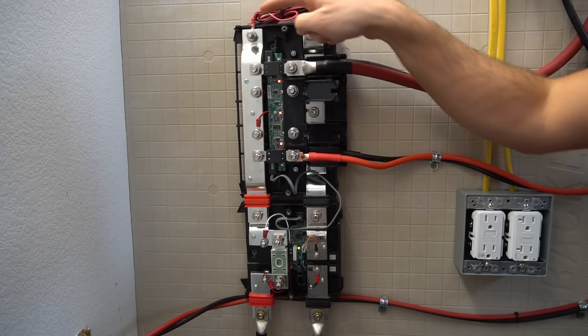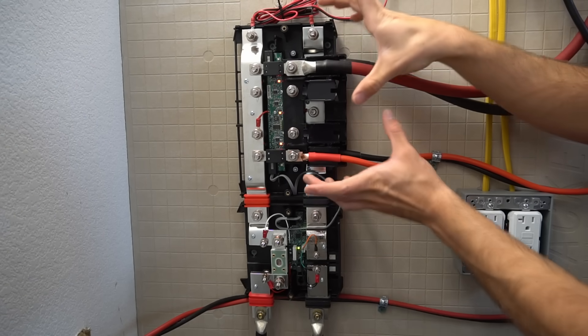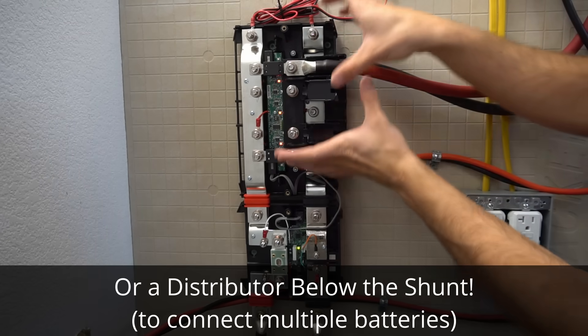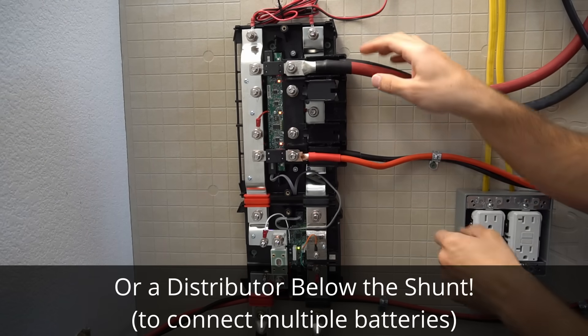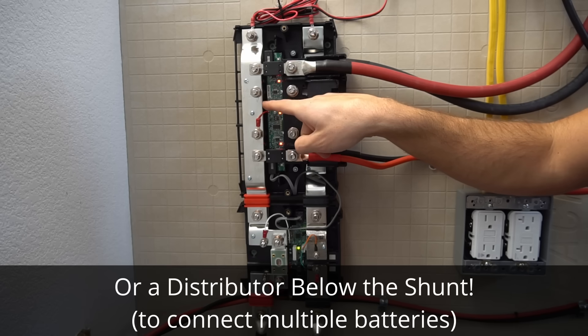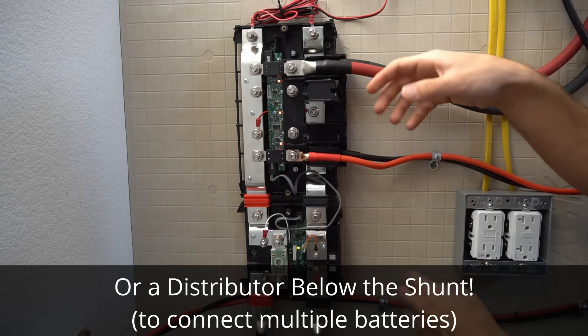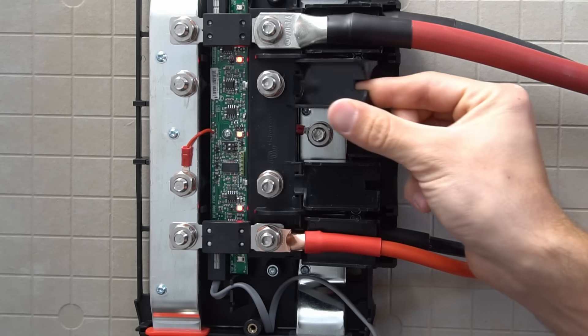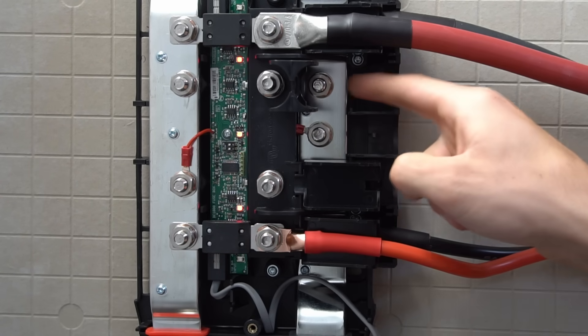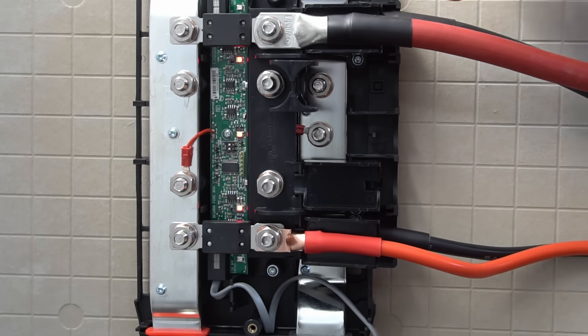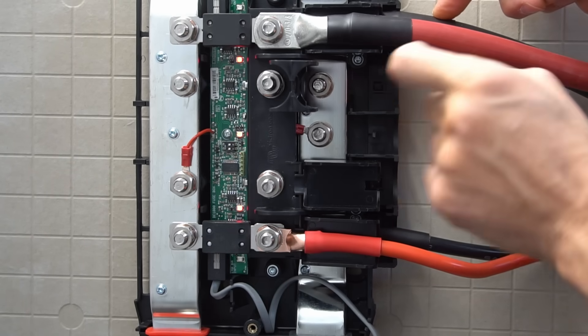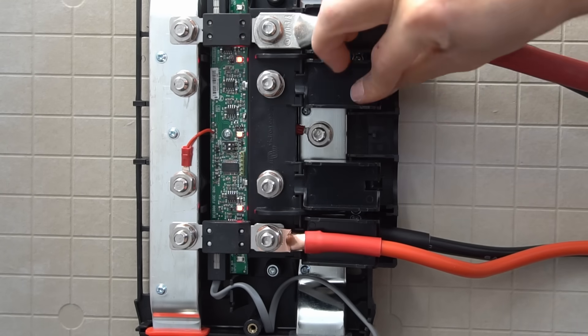Now the coolest thing is you have terminals up here and you can add another distributor onto this one. So you have one shunt distributor and as many distributors as you like. But this is limited to 1000 amps, so be sure to not exceed that. Now the cable management is quite interesting on this system. If you lift up these covers it will expose the negative bus bar.